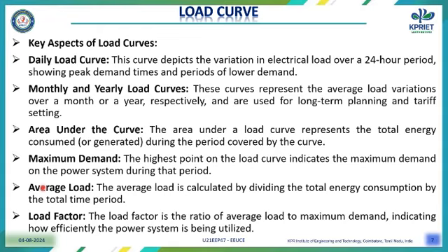Next, average load. The average load is calculated by dividing the total energy consumption by the time period. We can call this the total time period. Next, load factor. The load factor is the ratio of average load to maximum demand, indicating how efficiently the power system is being utilized.